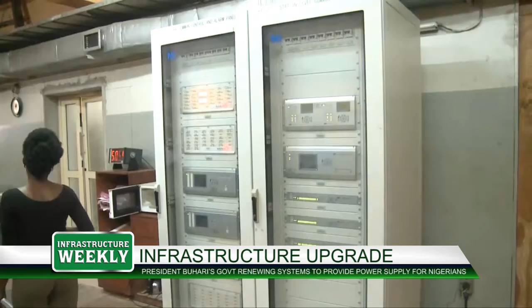Now when the temperature comes down, the air will go down and the air needs to be replaced, balancing the pressure, so no excess pressure. So when the air is returning inside, it passes through the silica gel. All this moisture in the environment will not be able to pass in with it. The moisture is bad for our windings and the working parts of the transformer, so this increases the working life of the transformer. The power transmission equipment installed include transformers, protective devices, metering circuits, as well as state-of-the-art control panels to facilitate the wheeling of more reliable power to the distribution companies and the people of Nigeria.